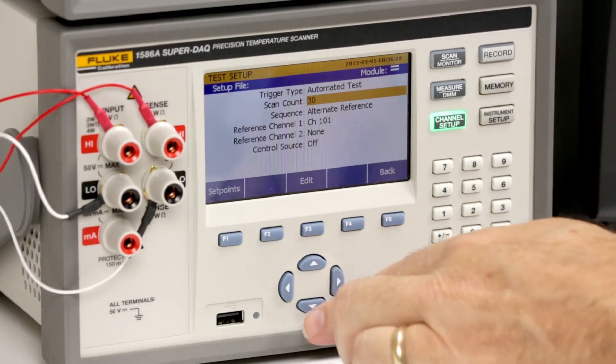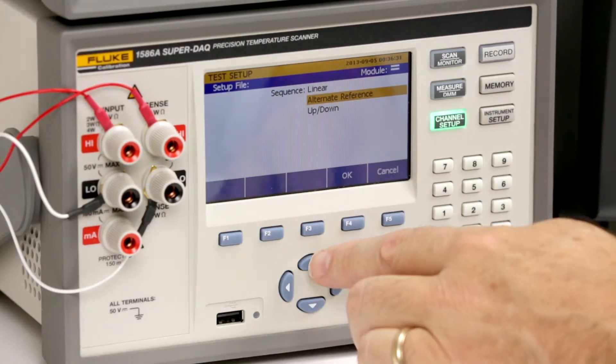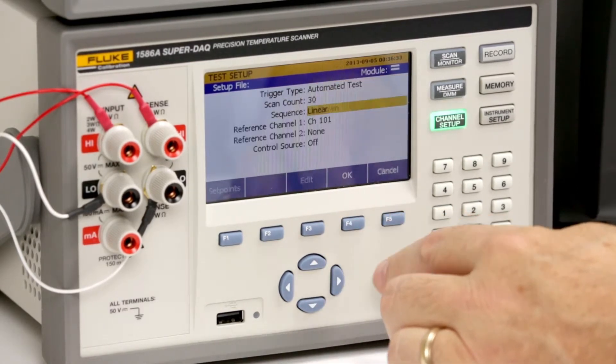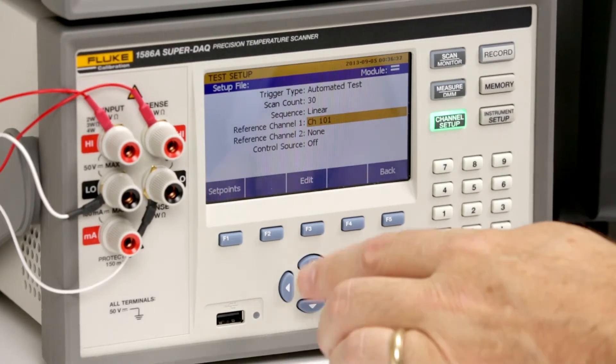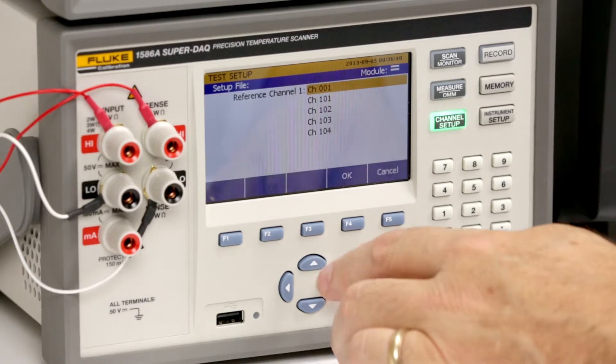Set the sequence to linear, which means the 1586 will scan the reference channel and unit under test channels sequentially. Designate a reference channel. We'll select the front panel reference channel 1.